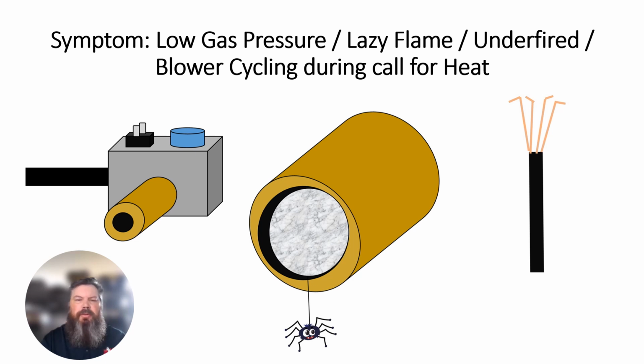The number one service call I get for early season mobile home furnaces on cleaning checks is going to be: it's acting like it's got low gas pressure, it's got a lazy flame, it's under fired. The blower is cycling on and off, but the flame never shuts down.